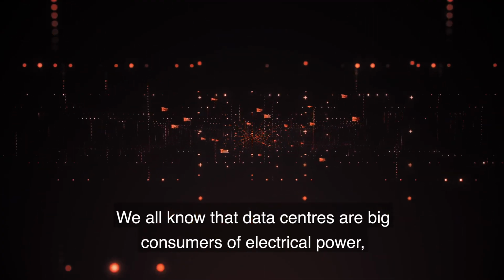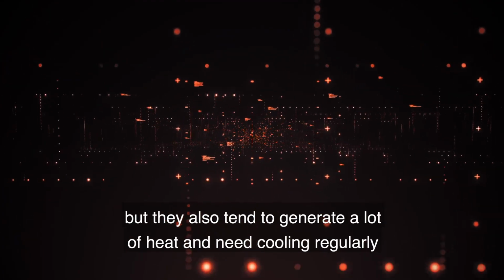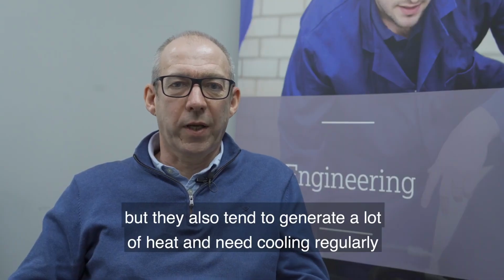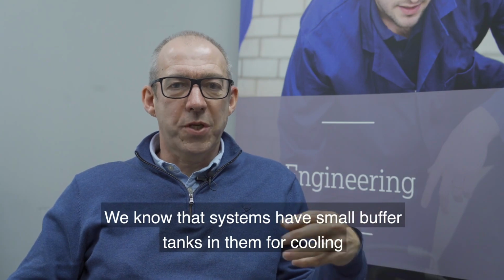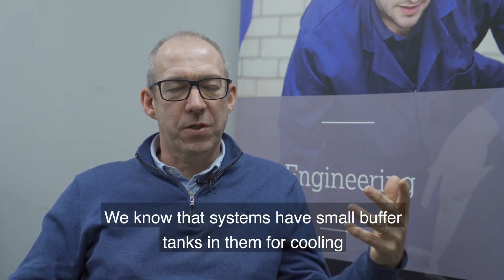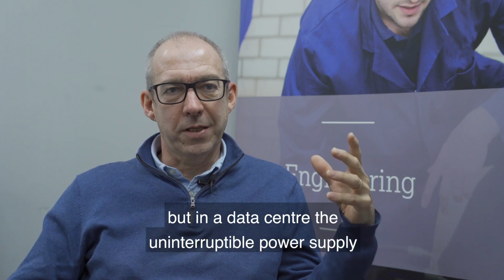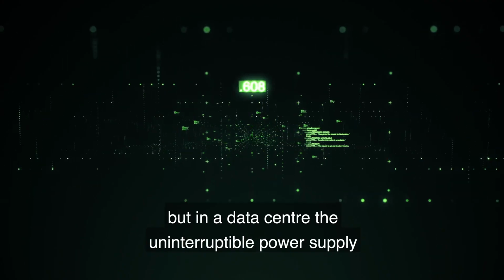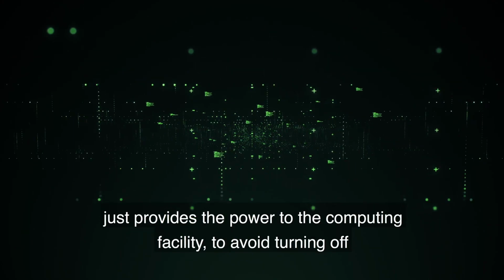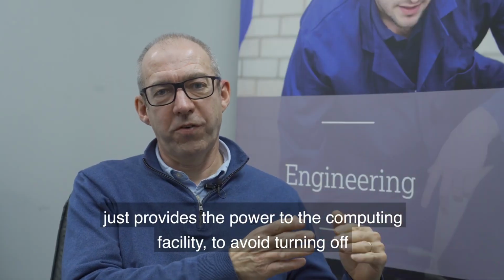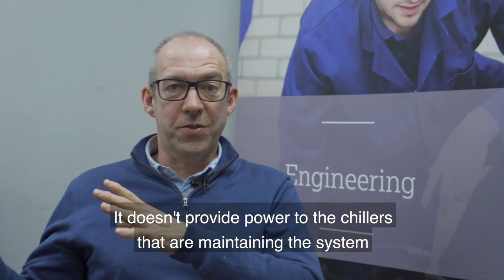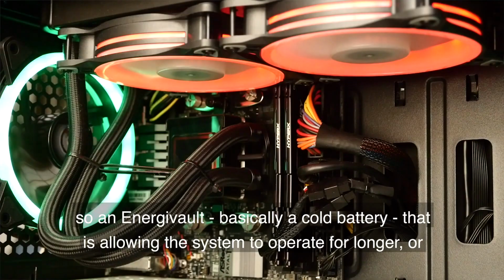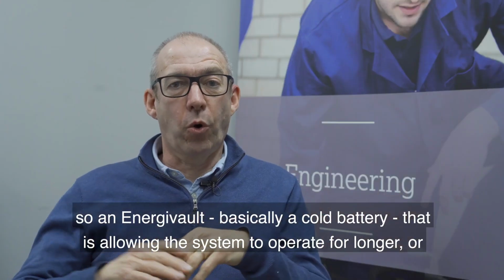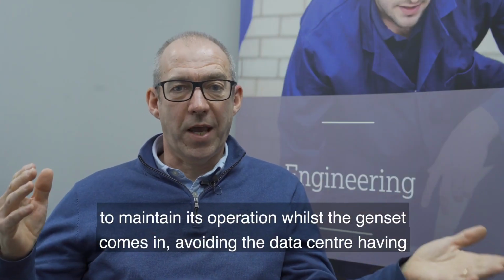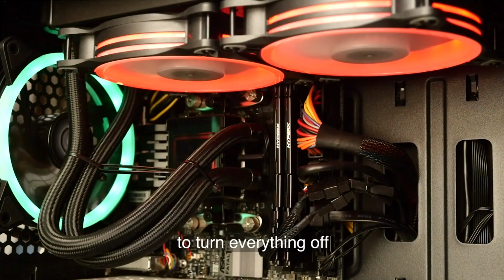We all know data centers are big consumers of electrical power, but they also generate an awful lot of heat and need cooling regularly. We know systems have small buffer tanks for cooling, but in a data center, the uninterruptible power supply just provides power to the computing facility to avoid turning off—it doesn't provide power to the chillers maintaining the system. So an Energivault is basically a cold battery that allows the system to operate for longer, or maintain operation whilst the genset comes in, avoiding the data center having to turn everything off.